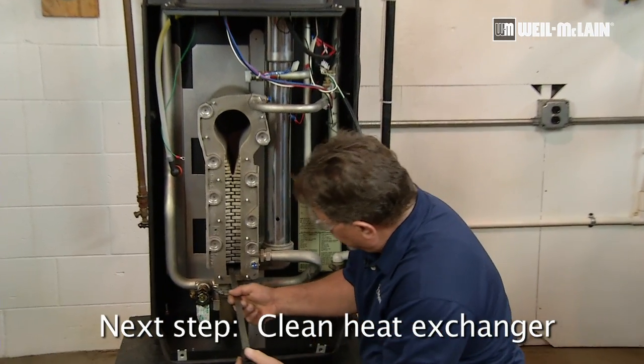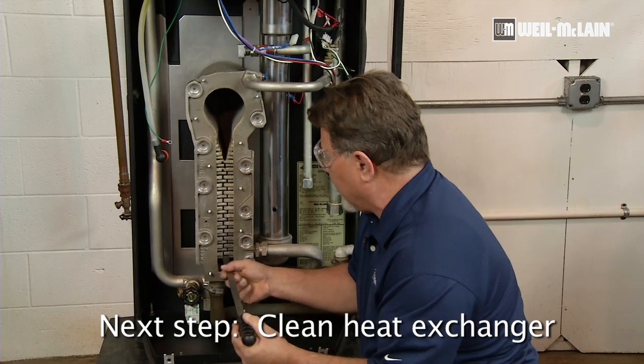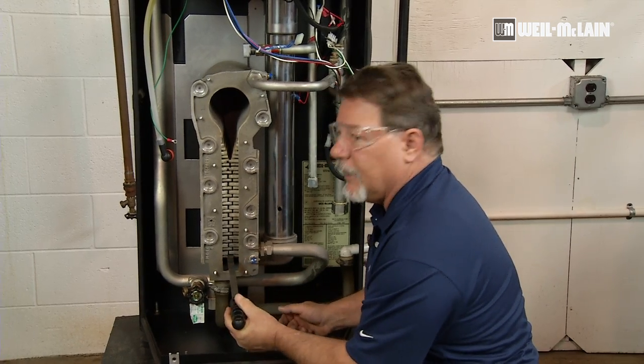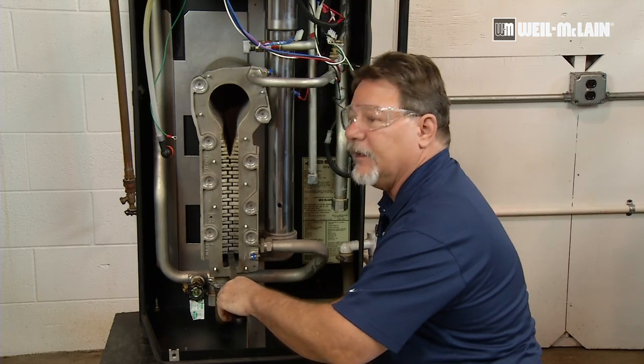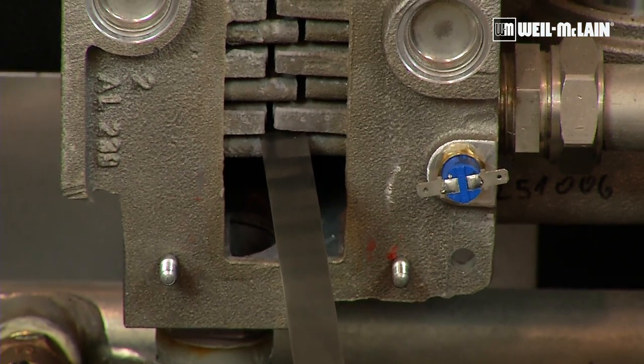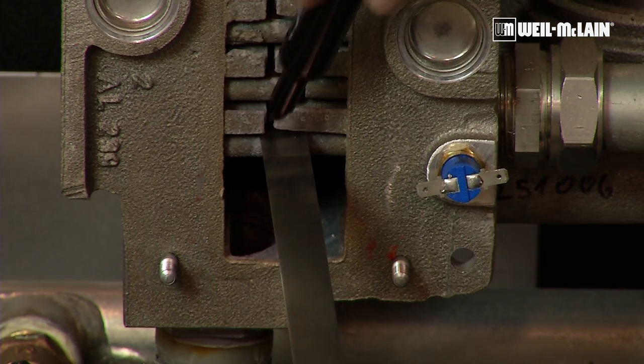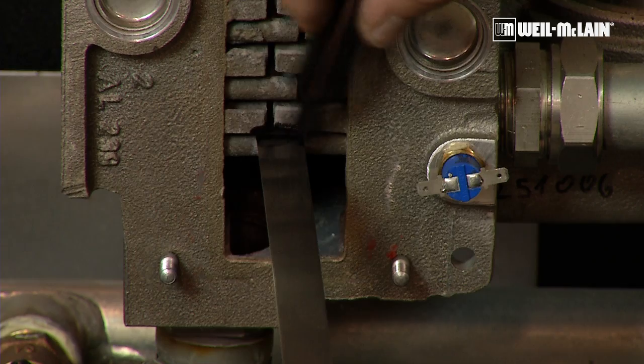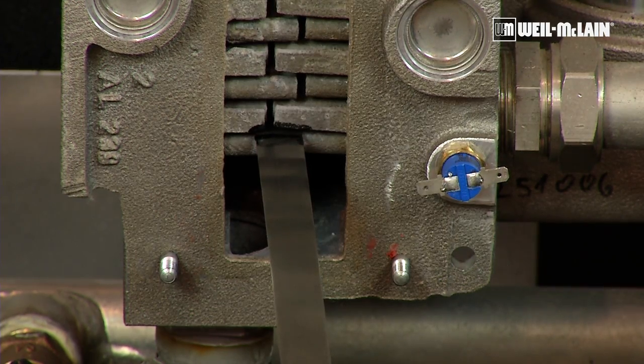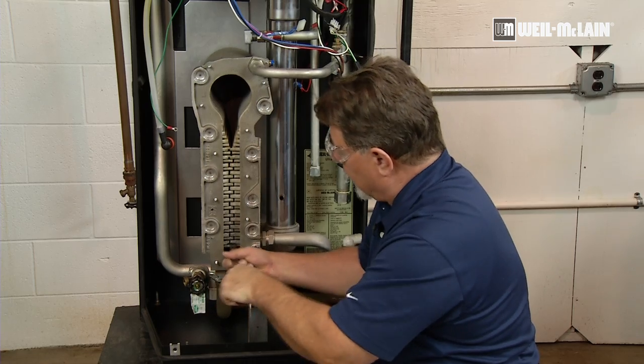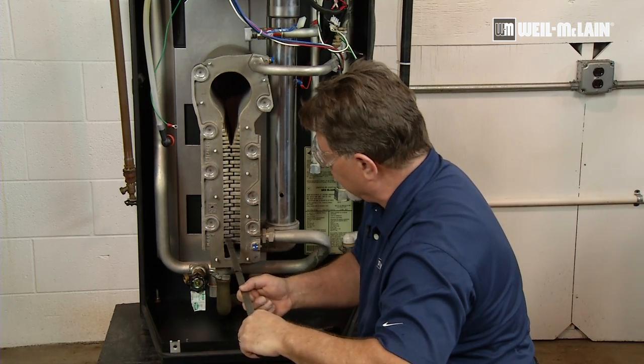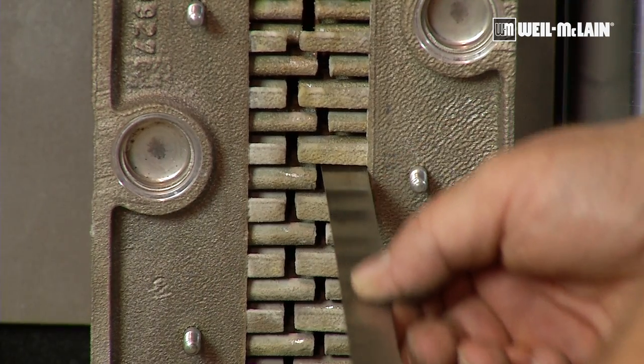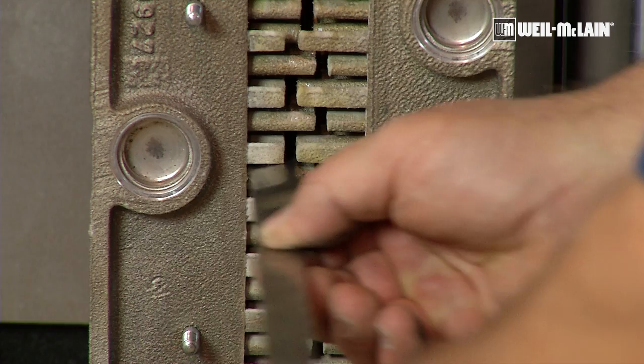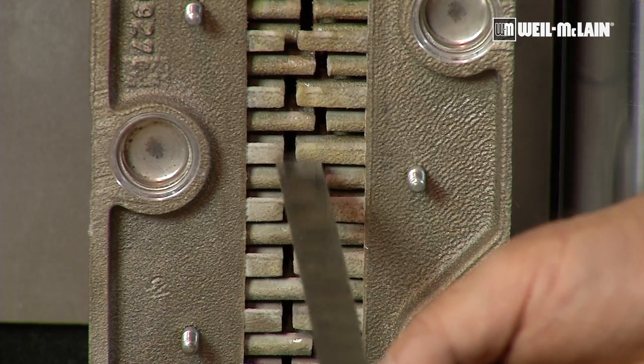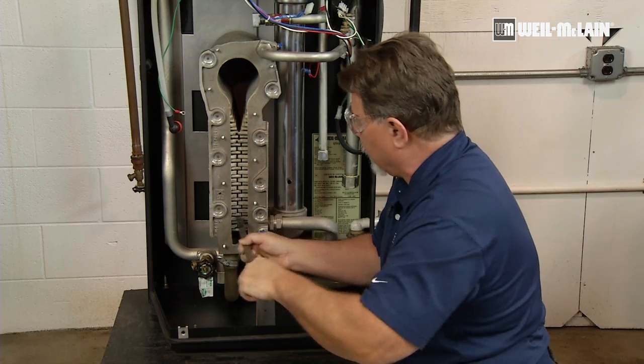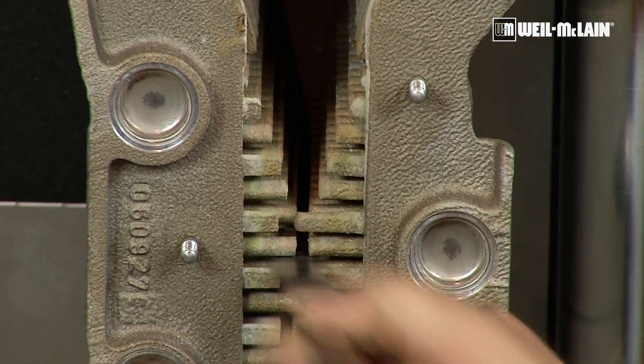We have our heat exchanger cleaning tool, and really the first thing that you need to do is insert it, get it all the way to the back of the heat exchanger. And then I take a marker and I mark on the blade where that depth is so that I'm consistent all the way across the top. And I'm just cleaning every row all the way back. We want to continue this all the way up to the very top, paying specific attention to make sure that we get all the debris pushed down to the bottom.